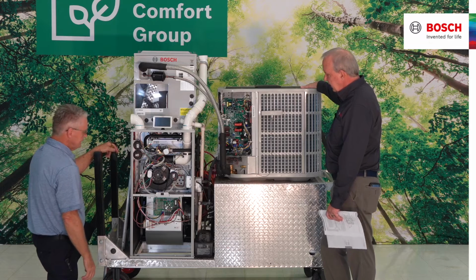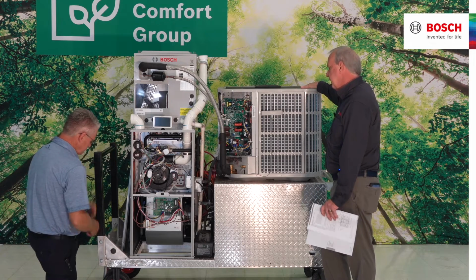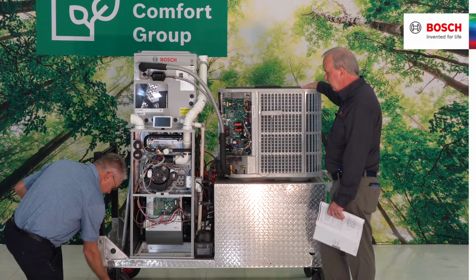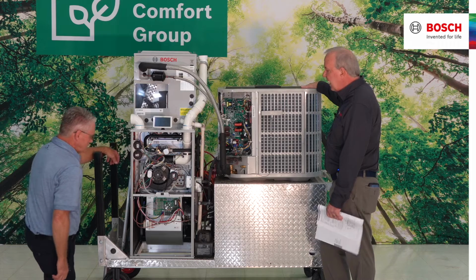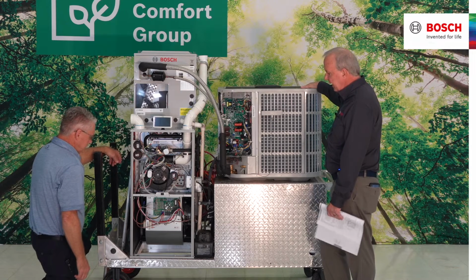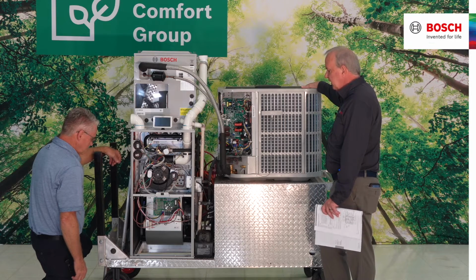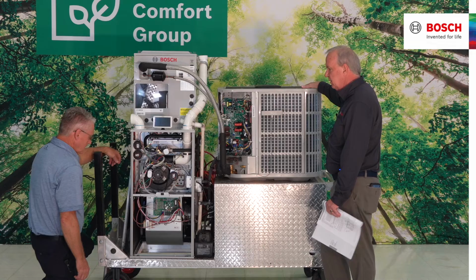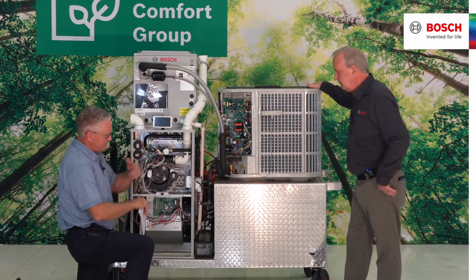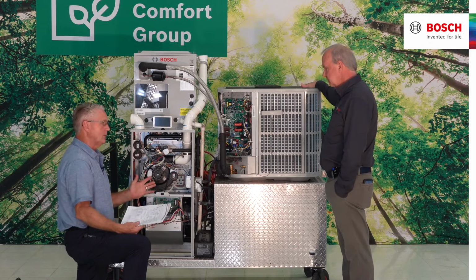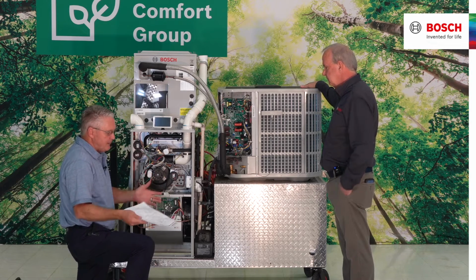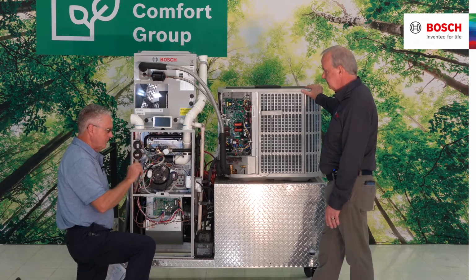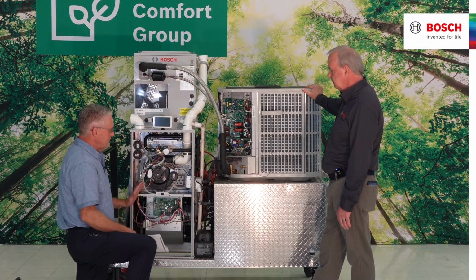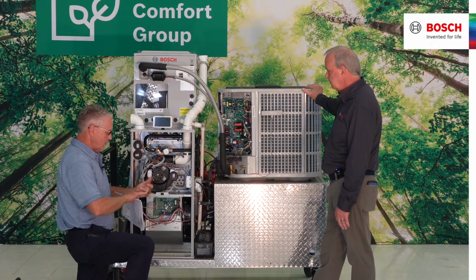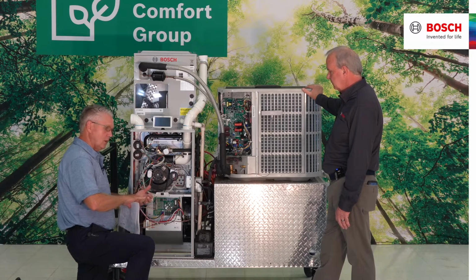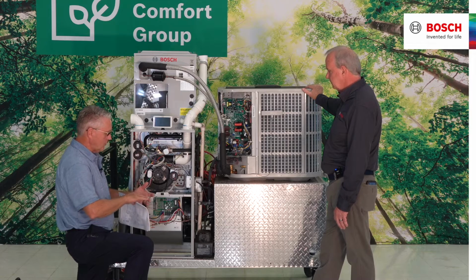Correct. Now, we know that static pressure and CFM are very critical. What are our options? What type of blower motor does this furnace have? And what options do we have as far as selecting or adjusting CFM and static pressure? Every furnace size from the 60 to the 120 is going to have a 5-speed blower motor. Those different speeds allow us to dial in the comfort, dial in the CFM for the delta T that's coming through this unit, whether we're on a low cool call or a low heat call, a high heat call or a high cool call.